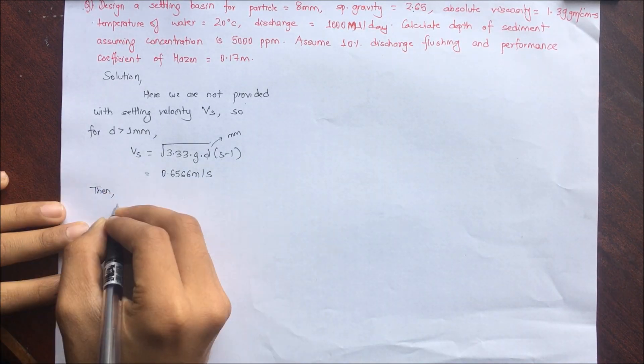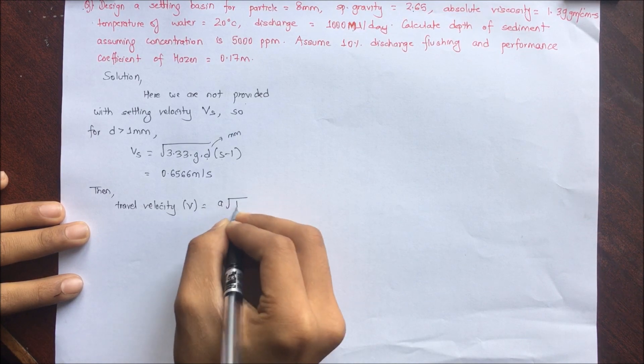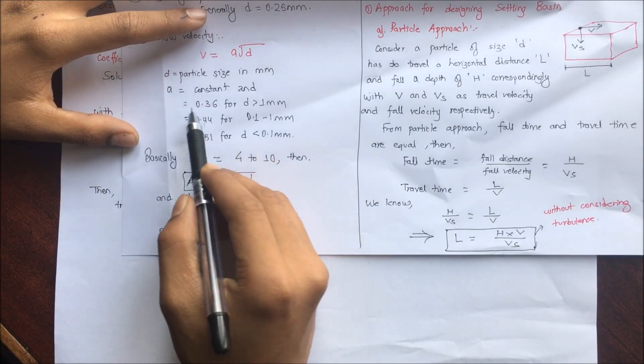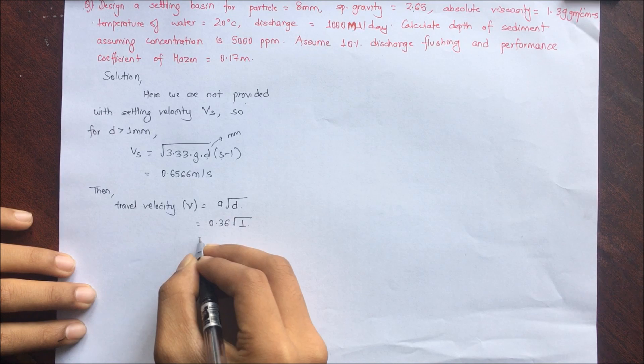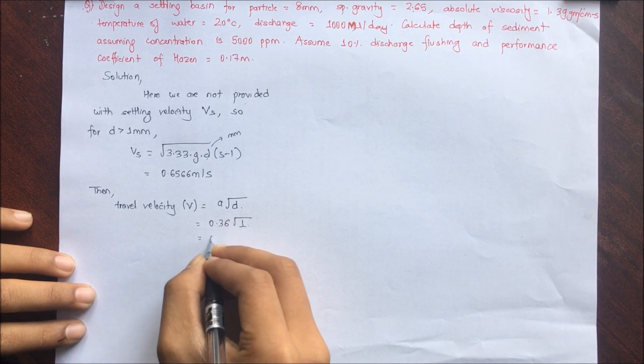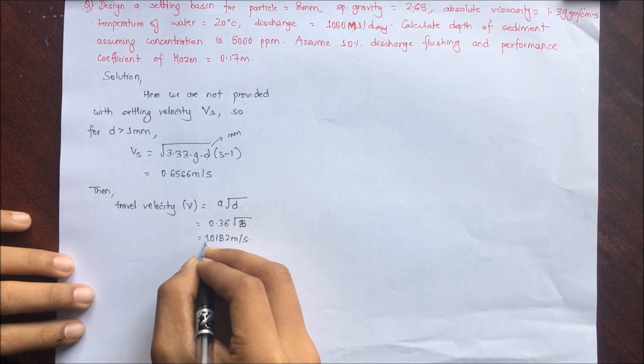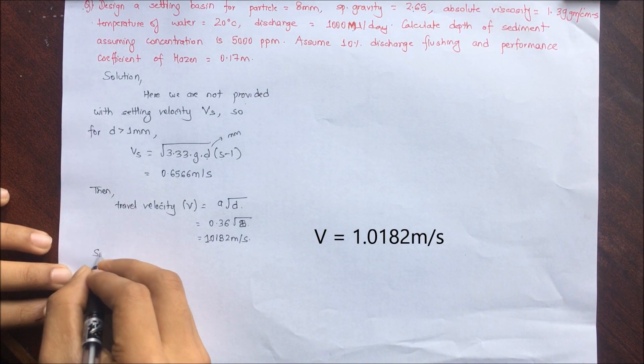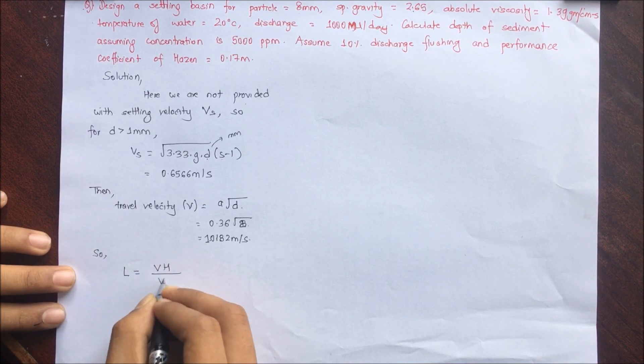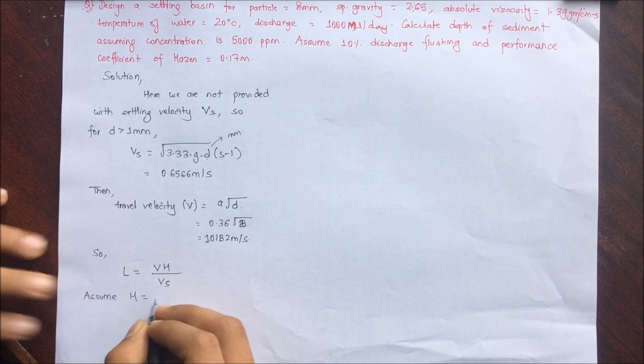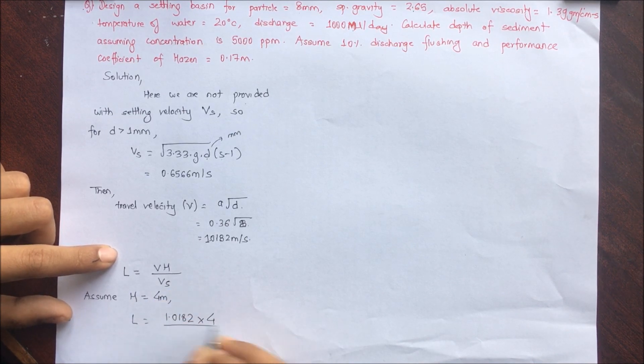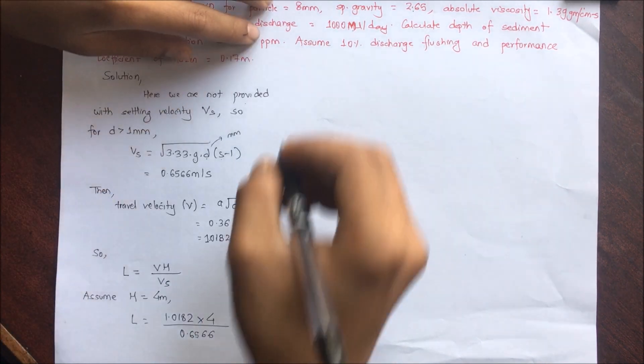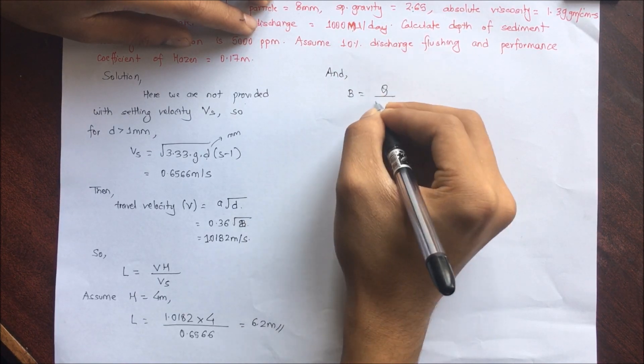Next, we determine the travel velocity v = a × √d, where a is a constant. For particle size greater than 1 mm, a = 0.36 and d = 8 mm, giving v = 1.0182 m/s. From the particle approach, length L = (v × H) / vs. Assuming H = 4 m, L = (1.0182 × 4) / 0.6566 = 6.2 m. This is the length without considering turbulence.